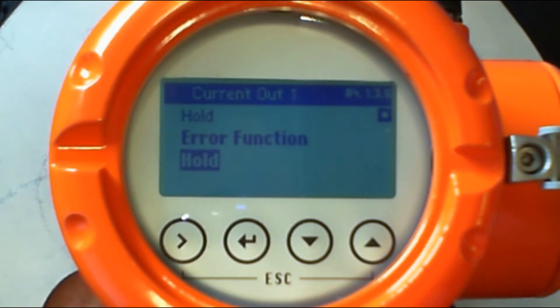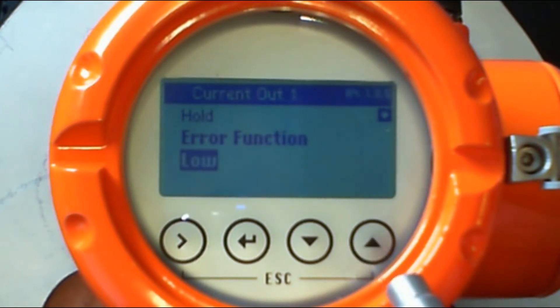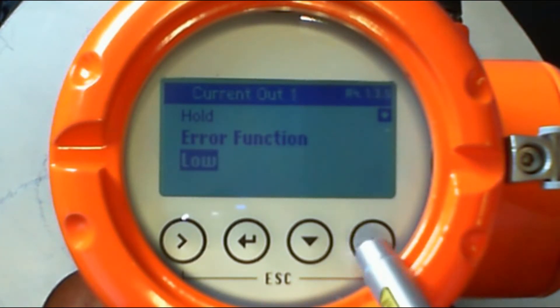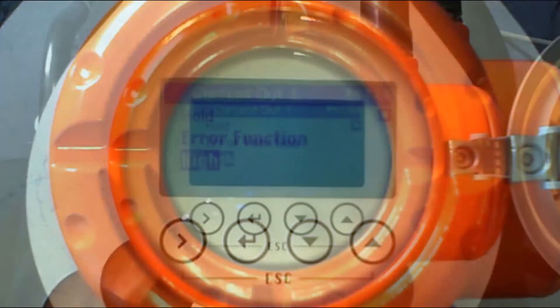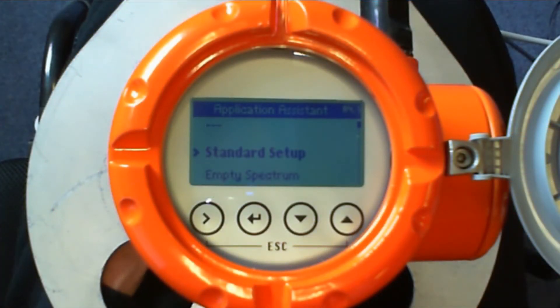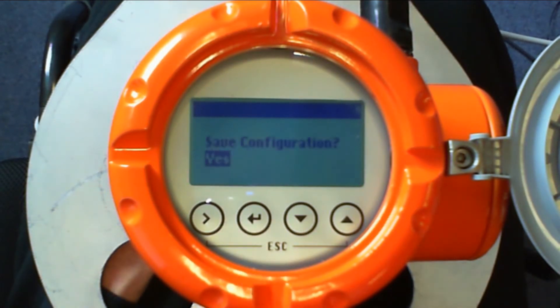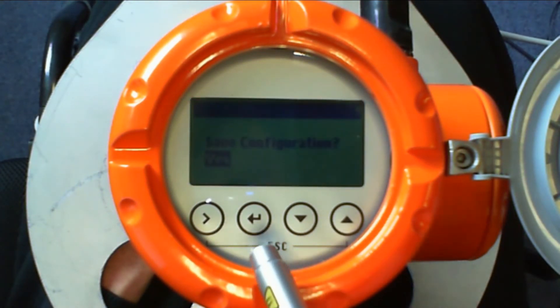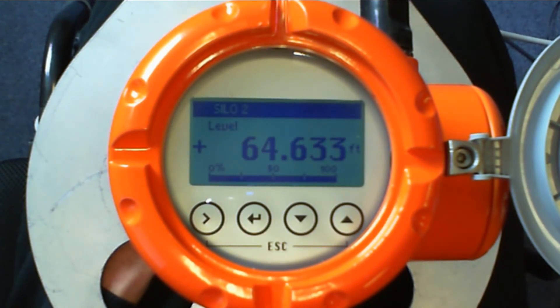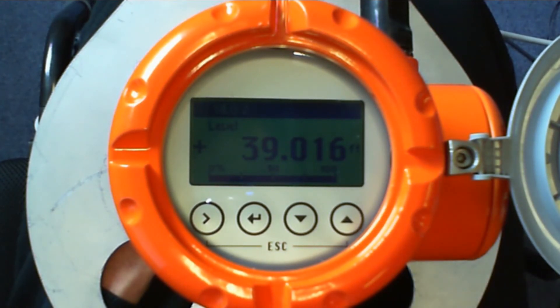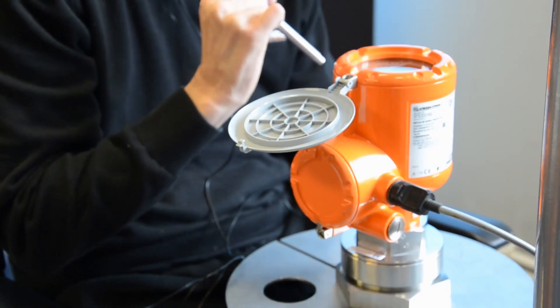We need to set the output function should the device fail in some way. Options here are low, high, or hold. For many applications we want to show a high output so that the silo isn't filled by accident. This completes the standard setup and we can now navigate back through the menus to return to run mode. Before we do that, it will ask if we want to save the configuration — we want to say yes. Our tag has now changed and our level is now showing the value in feet. This is now set up for feet measurement of level in the silo.